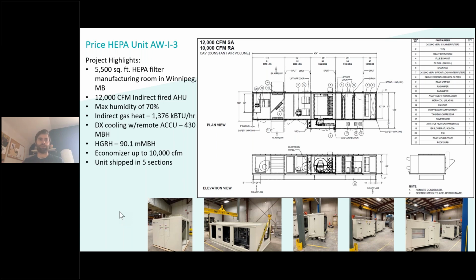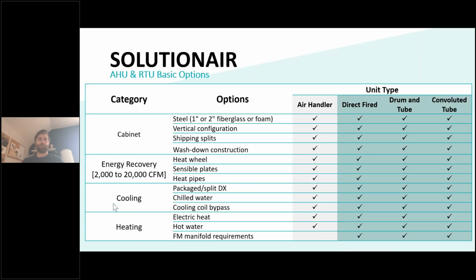And we needed to provide 12,000 CFM of indirect fired air handler. There was a max humidity of 70% allowable in that space. And we achieved that with a remote DX package with hot gas reheat. Also, there's an economizer section within the unit, but all in all, it was shipped in 5 segments or sections, shipped off to the Winnipeg's main plant at Price headquarters, and assembled on the roof.